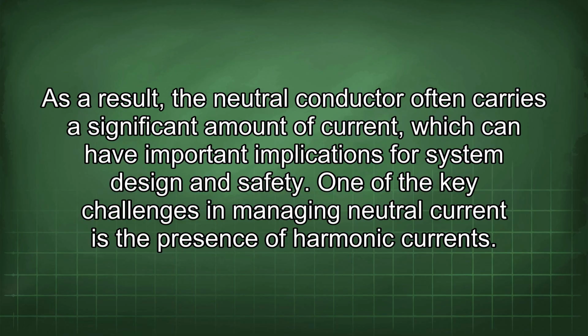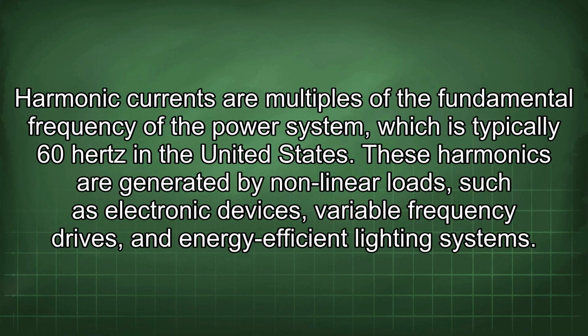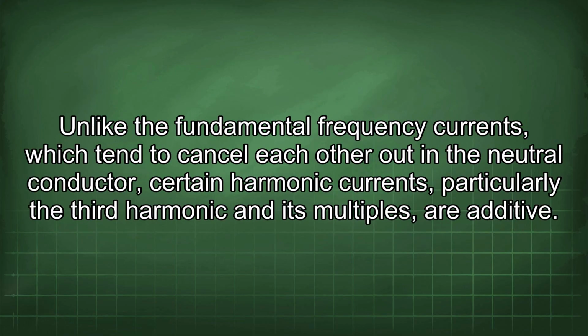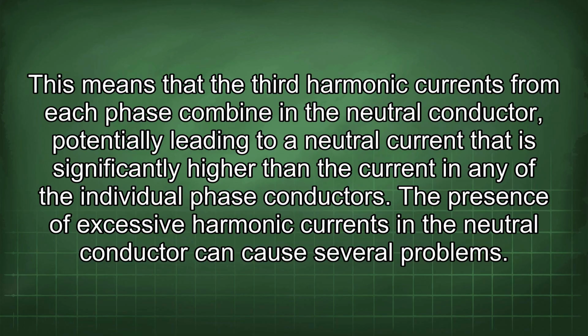One of the key challenges in managing neutral current is the presence of harmonic currents. Harmonic currents are multiples of the fundamental frequency of the power system, which is typically 60 Hz in the United States. These harmonics are generated by nonlinear loads such as electronic devices, variable frequency drives, and energy-efficient lighting systems. Unlike the fundamental frequency currents, which tend to cancel each other out in the neutral conductor, certain harmonic currents, particularly the third harmonic and its multiples, are additive. This means that the third harmonic currents from each phase combine in the neutral conductor, potentially leading to a neutral current that is significantly higher than the current in any of the individual phase conductors.